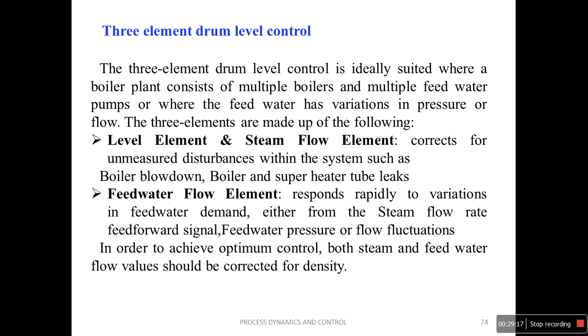So the 3 parameters are measured. It is a combination of feed forward, feedback, and you can say cascade also. In the 3 element control, we measure all these 3: the level of the drum, the steam flow, as well as the present feed water flow rate. Depending upon all these 3 measurements, the controlling variable is again the feed water only, so we change the feed water flow rate. Like this, the boiler level can be controlled.